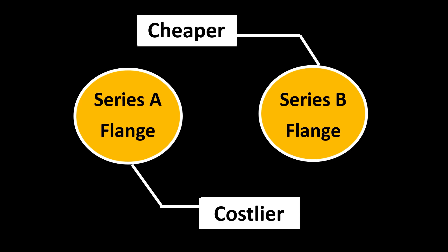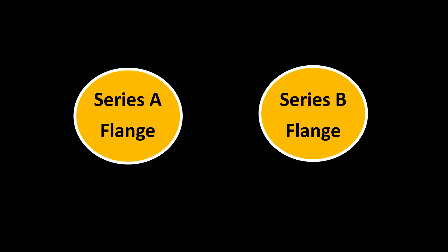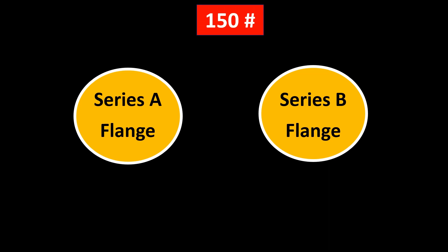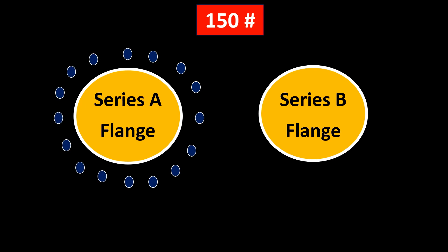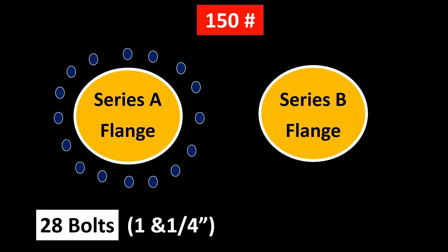But this is not the most important difference. The difference lies in something else altogether. So imagine you have a 150 rating Series A and B flanges. Series A will have 28 bolts of 1 and 1/4 inch diameter.